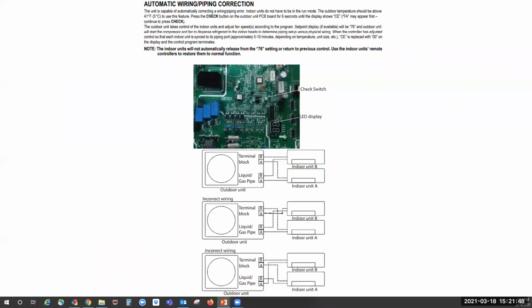Automatic wiring and piping fix. This is a good way to test, especially on multi-head systems. You could have something crossed. However, the main problem with this is it's not recommended. It's preferred that you physically change the wiring to match the piping.